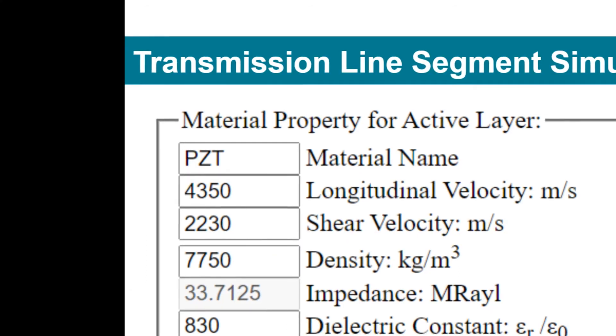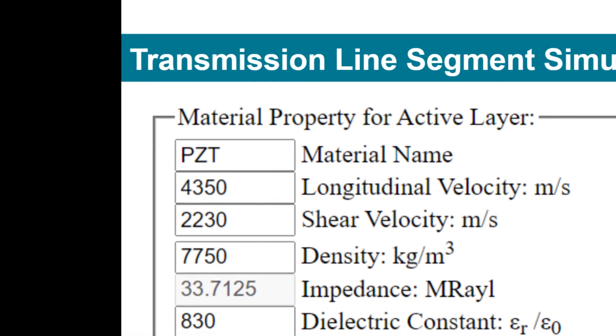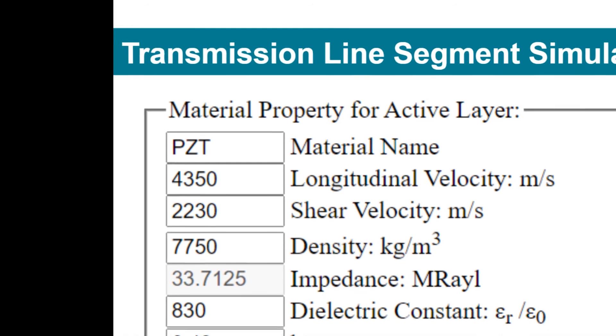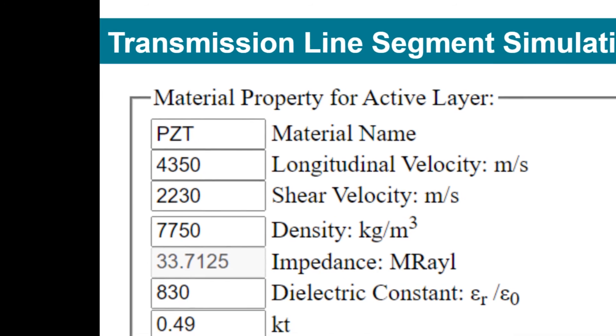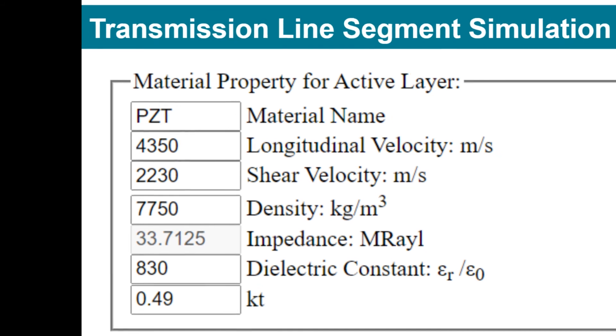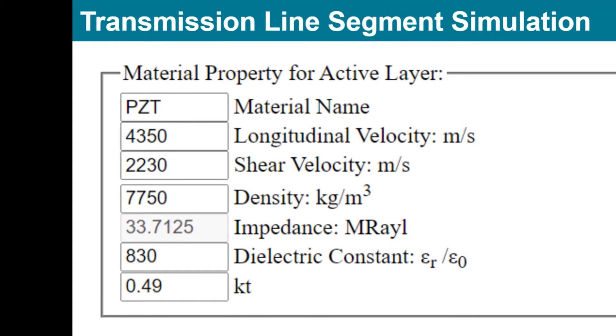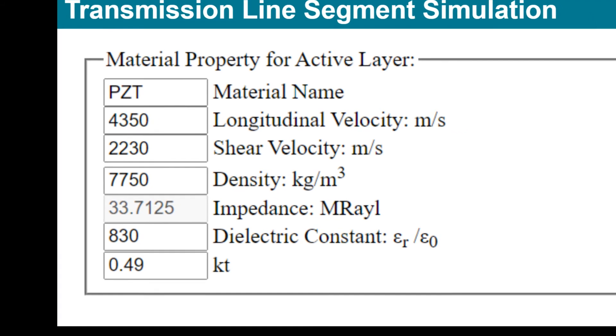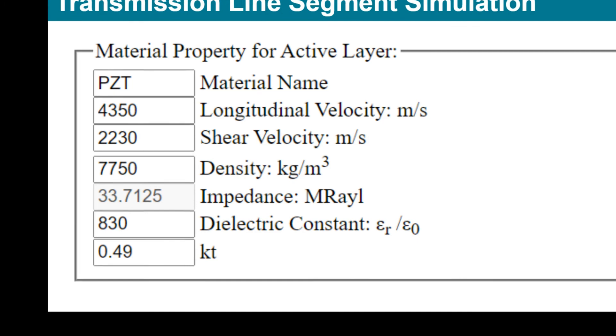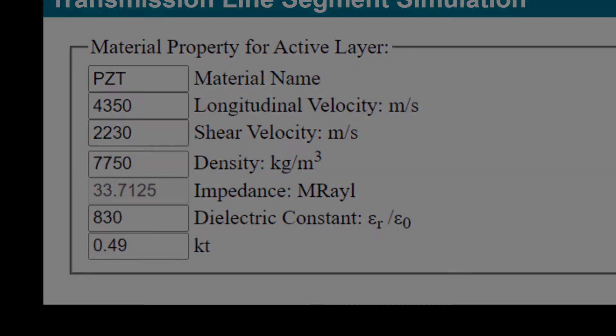All the acoustic layers, including the backing layer, PZT layer, acoustic medium, and matching layers, are simulated by segments of the transmission line. The wave speed of the transmission line is the acoustic speed of the material, and the length of the transmission line is the thickness of the corresponding layer.